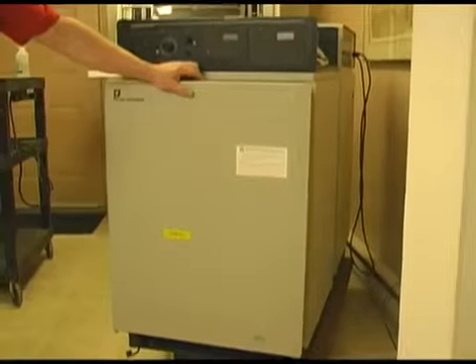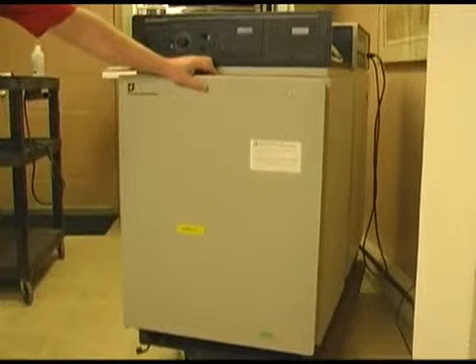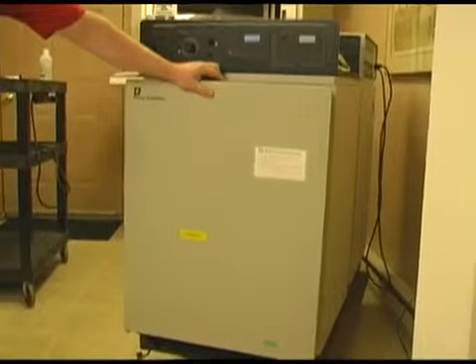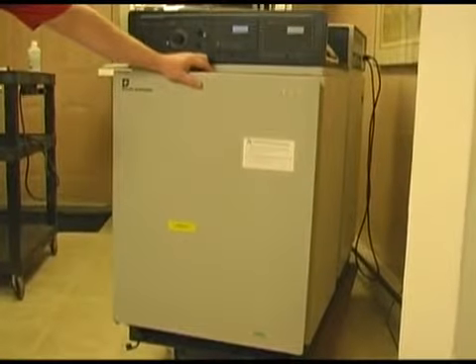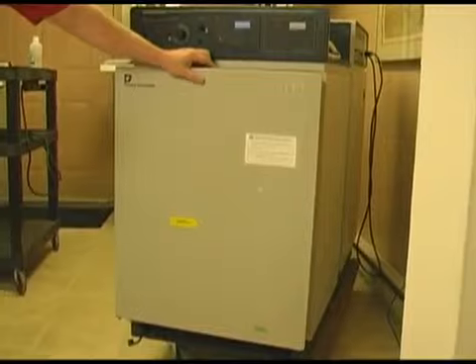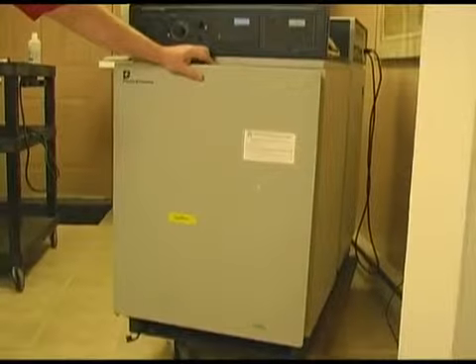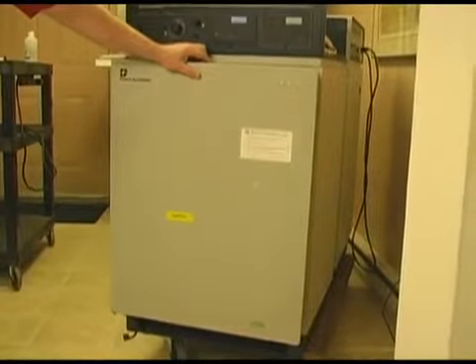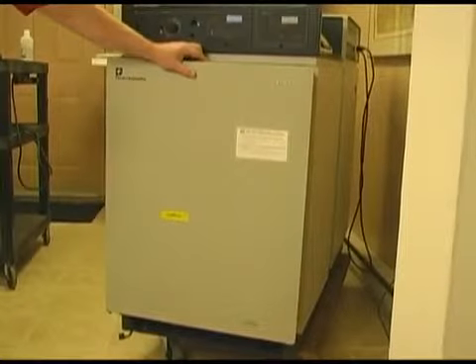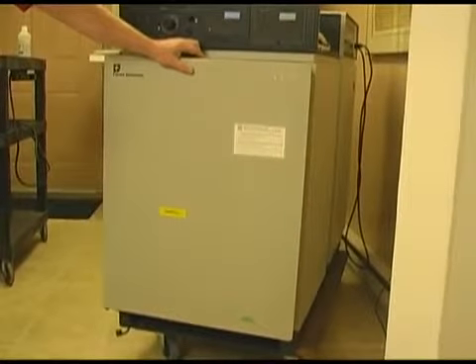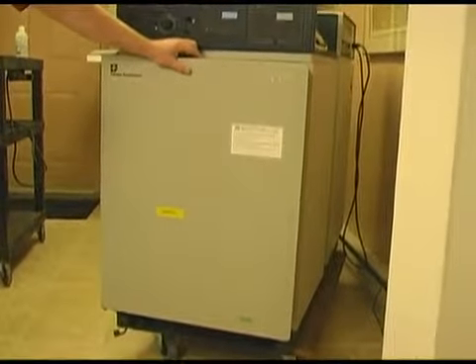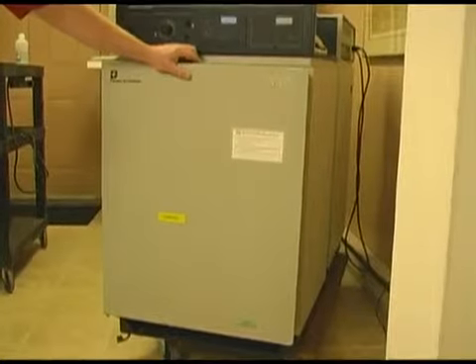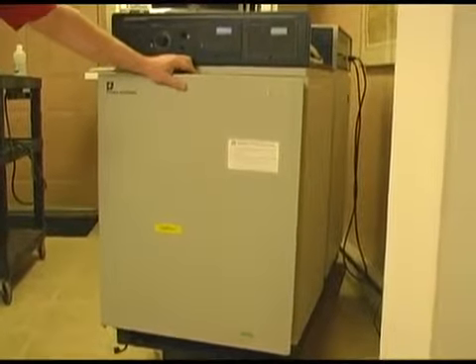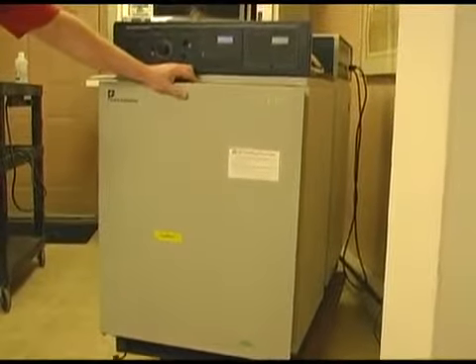The advantage to the air is the fact that it is quick. It's quick to get to the set point, as an example, 37 degrees. Whereas a water jacket incubator would take 24 hours to get to that temperature. In fact, that would be my recommendation, if you're setting this up, is to put the water in it and let it go for 24 hours.